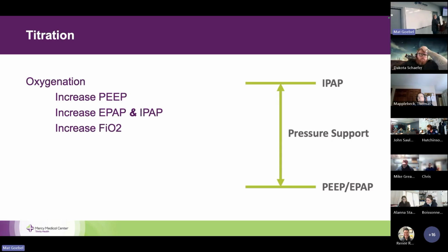Now, if my machine is PEEP plus pressure support and I increase the PEEP, it's automatically doing the same amount of pressure support when you increase the PEEP. So that is an advantage, depending on how the machine is configured by the manufacturer, that it can be a little bit more straightforward for you to remember.